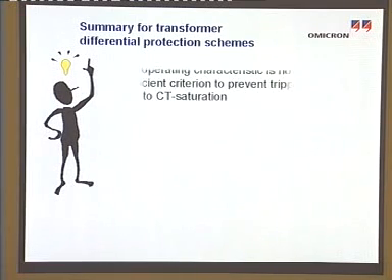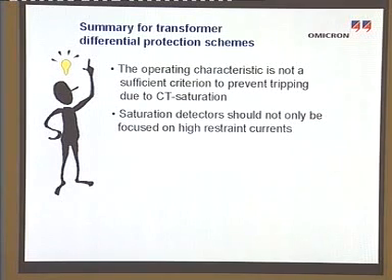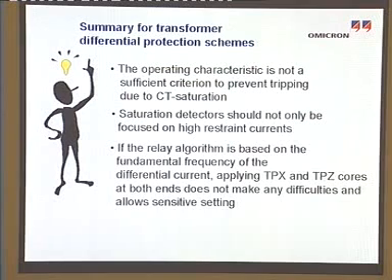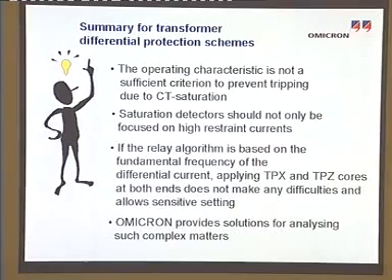As a conclusion, the following essential findings can be highlighted. The operating characteristic is not sufficient on its own to prevent tripping due to CT saturation. Saturation detectors should not only be focused on high-restraint currents. If the relay algorithm is based on the fundamental frequency of the differential current, applying TPX and TPZ cores at both ends does not create any difficulties and allows sensitive setting. Omicron provides solutions for analyzing and testing such complex situations.